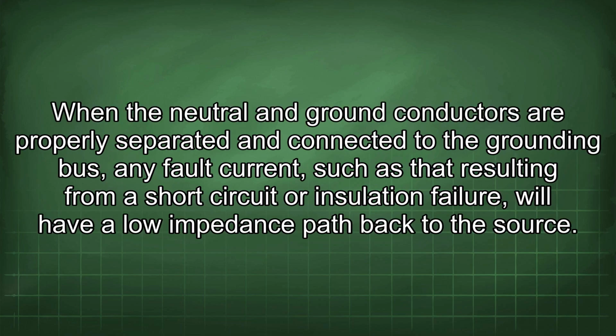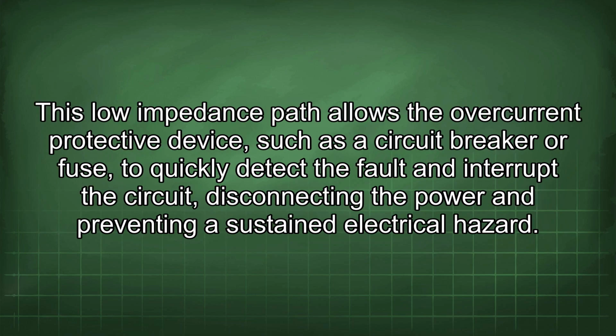When the neutral and ground conductors are properly separated and connected to the grounding bus, any fault current, such as that resulting from a short circuit or insulation failure, will have a low impedance path back to the source. This low impedance path allows the overcurrent protective device, such as a circuit breaker or fuse, to quickly detect the fault and interrupt the circuit, disconnecting the power and preventing a sustained electrical hazard.